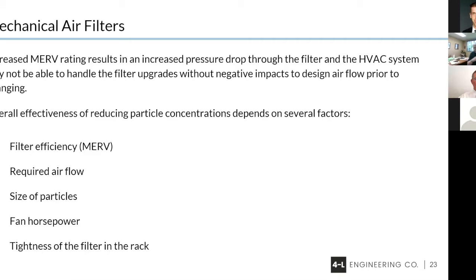In the future, you'll hear me talking about ECM motors, which will be going away from these 3-speed motors that we're accustomed to seeing in houses. We'll be using an ECM motor that can go up to around 1 inch of total static. One of the things that people should realize is the tightness of that filter in the frame. It should be tight in the filter rack. There should be no gaps that allow air to bypass. It needs to effectively seal. Next slide.